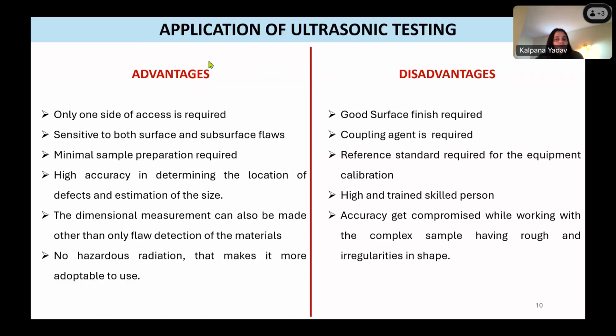A good surface finish is required. If the surface of the sample is irregular, the transmission of energy is not going to be perfect. There is going to be some loss of energy, and you are not going to get a better signal when it is reflected from the sample. So a good surface finish is required, and a coupling agent is also required. You cannot test without a coupling agent.